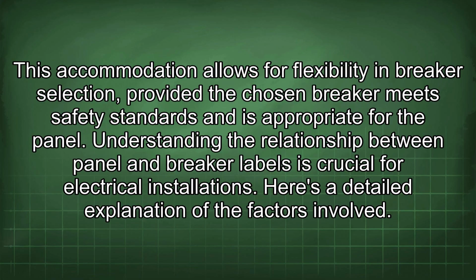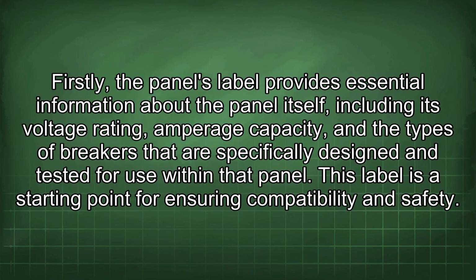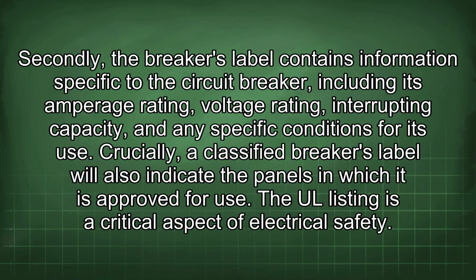Here's a detailed explanation of the factors involved. Firstly, the panel's label provides essential information about the panel itself, including its voltage rating, amperage capacity, and the types of breakers that are specifically designed and tested for use within that panel. This label is a starting point for ensuring compatibility and safety. Secondly, the breaker's label contains information specific to the circuit breaker, including its amperage rating, voltage rating, interrupting capacity, and any specific conditions for its use. Crucially, a classified breaker's label will also indicate the panels in which it is approved for use.